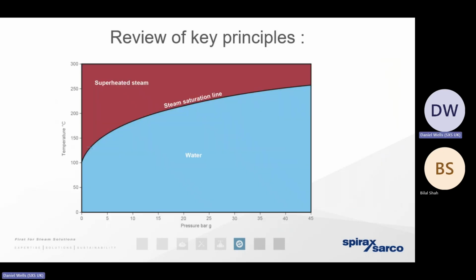And another relationship I want to refer to is what we call the pressure temperature relationship. So as we've mentioned, water at 0 bar gauge boils at 100 degrees, which tells us the temperature of the steam. At 10 bar gauge, water boils at 184 degrees, therefore so is the steam. But if we've got a heat exchanger that needs to operate at 130 degrees, for example, it tells us that we can achieve that just by manipulating the pressure with those very, very basic controls. Remember what I said, when steam gives up its heat energy and condenses, it doesn't cool down. So this is the pressure temperature relationship for both steam and for condensate.